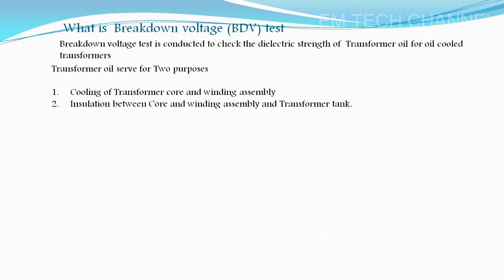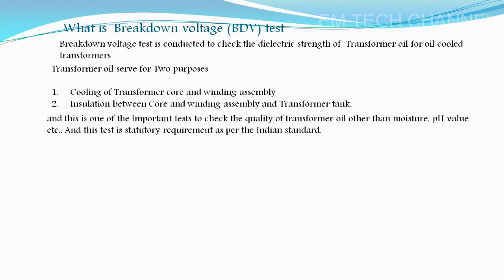It is one of the important tests to check the quality of the transformer oil, other than moisture, pH value, etc. Even though there are 8 to 10 tests that are to be carried out on transformer oil and are mandatory, the breakdown voltage test is one of the important tests, and we are going to see it today in this video. It is a statutory requirement as per Indian standard.